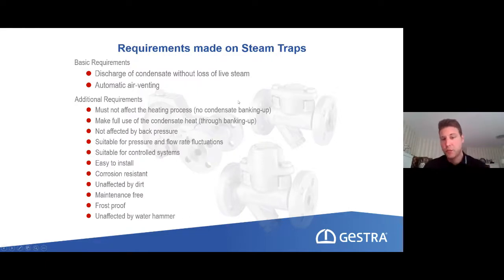Some steam traps have no banking up of condensate, so every amount of condensate coming to the steam trap will be discharged immediately. Some other steam traps do have a little banking up of condensate. It's just part of their working principle, so it's just normal. But that tells us they have a different location in the steam system. They have to be installed somewhere else and not directly in the heating process, because we don't want a banking up of condensate in the heat exchanger. This will prevent the heat transfer and we cannot heat up the product anymore.